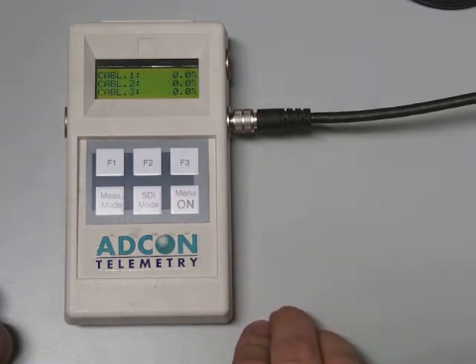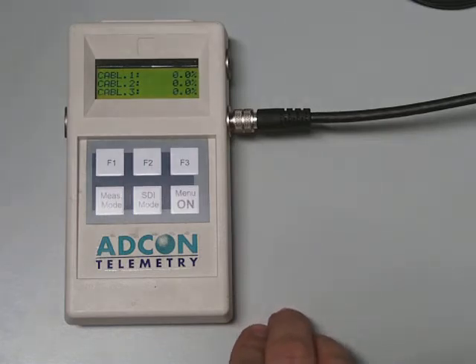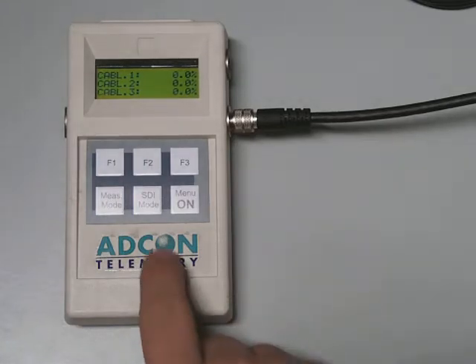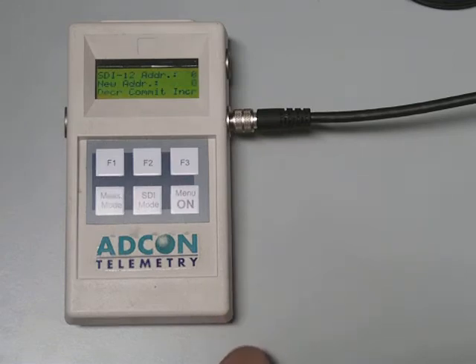A511 will start up in analog mode and show pins 1 to 3 of the 7-pin sensor connector to the left of this device. Now switch it to the SDI12 mode by pushing the SDI button briefly. A511 will automatically check if any SDI12 sensors are connected. Please note that you can connect only one sensor at a time. If a sensor is found, the top line of your display will show you the address of the sensor. In this specific case, it's running on address 0.